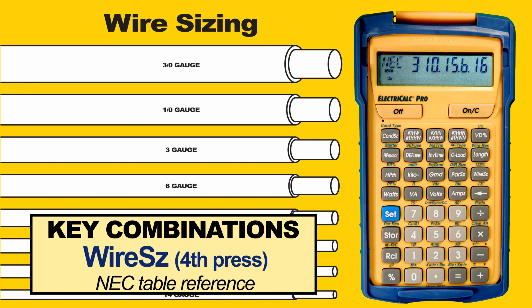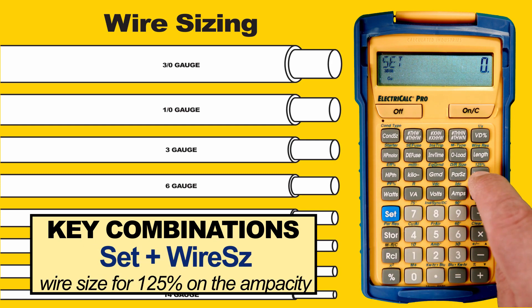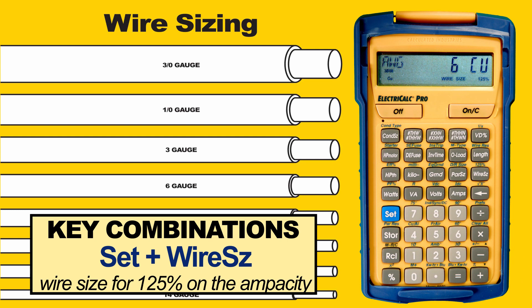This example has been for a 100% wire sizing situation. If you have a motor load and need to do it at 125% on the ampacity, press Set then Wire Size. By pressing Set first we are selecting the second function of the Wire Size button, as indicated on the yellow plastic case right above the button where we see 125%. We now see 125% indicated on the display along with the new wire size — in our case, number six is what we need to use.